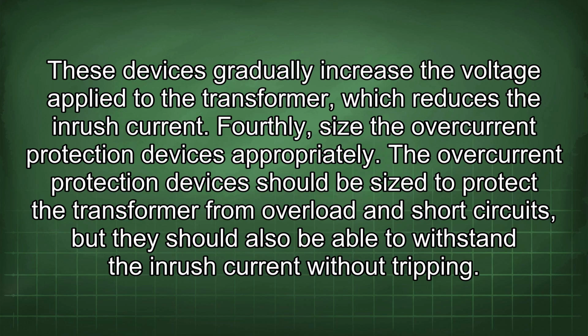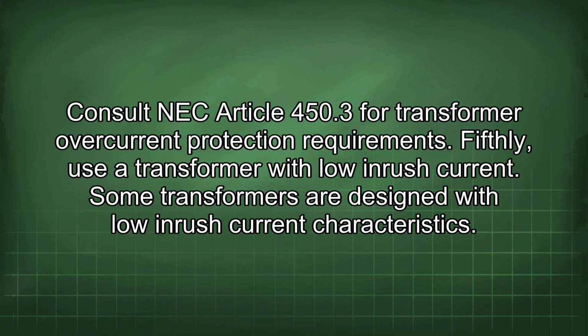Fourthly, size the overcurrent protection devices appropriately. The overcurrent protection devices should be sized to protect the transformer from overload and short circuits, but they should also be able to withstand the inrush current without tripping. Consult NEC Article 450.3 for transformer overcurrent protection requirements.